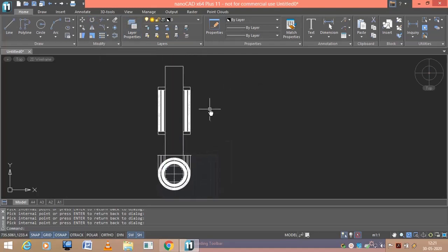Since the given problem is a 3-phase one, for the center to center distance, by using the magnetic circuit you can easily find out that the center to center distance is 250 plus 290. 250 is nothing but the width of the limb, and 290 is the width of the window. So together it is 540. That is your center to center distance.